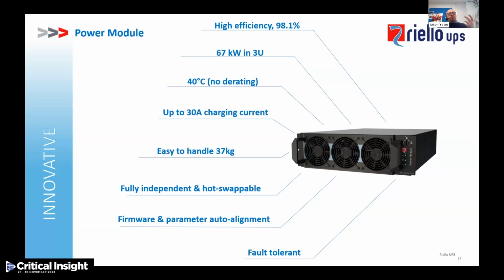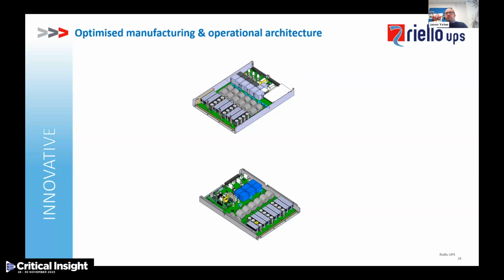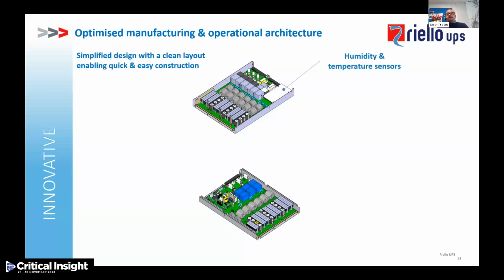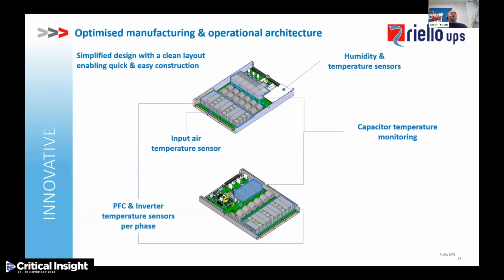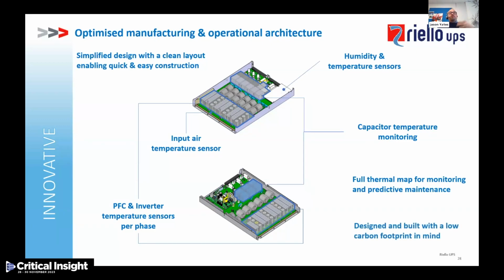So it's not just about that, but we've also looked at the optimization in terms of the manufacturing and the operational architecture of the module. The module has been built with a simplified and clean layout, which enables quick and easy construction, close connections for reduced losses. It's got humidity and temperature sensors. It's got input air temperature sensors. They have capacitor temperature monitoring, and they have power factor correction and inverter temperature sensors per phase. Basically, we've implemented a full thermal map for monitoring and predictive maintenance. But most importantly, we've designed and built with the low carbon footprint in mind.